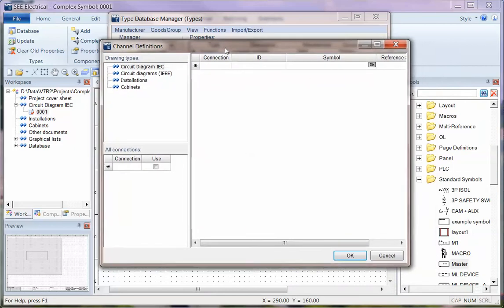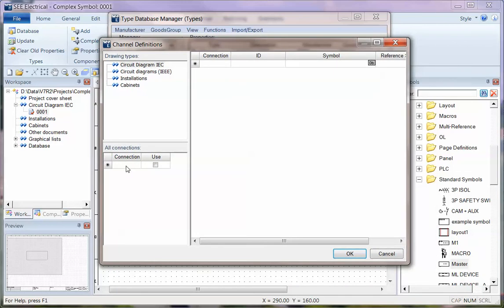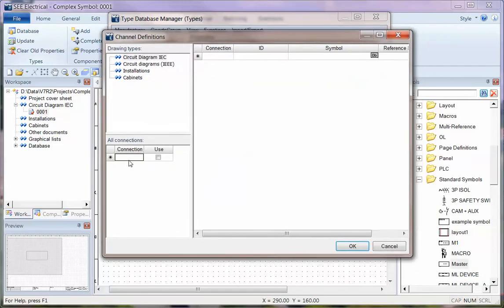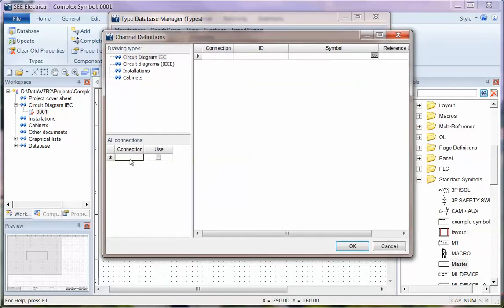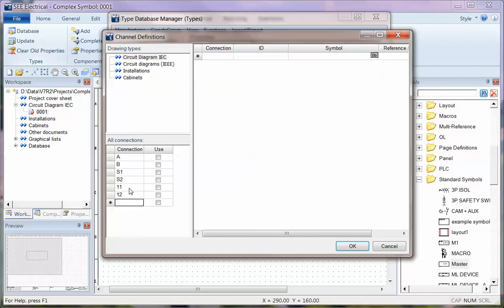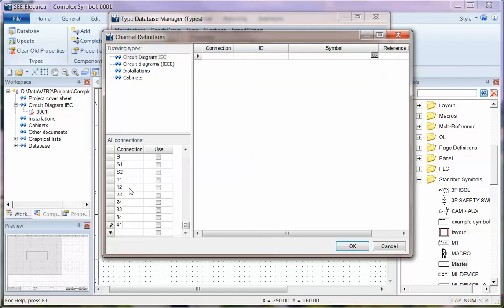And what I can do is type in the connections that I want on there. Now, at the moment, I hadn't really defined these properly. So I'm going to just type these in. The first four are on the main symbol, A, B, S1 and S2. I've then got some contacts normally closed first. So I'm going to put that as being 11, 12, two opens, 23 and 24 and 33 and 34. And the last one, which I'm going to put is 41 and 42.